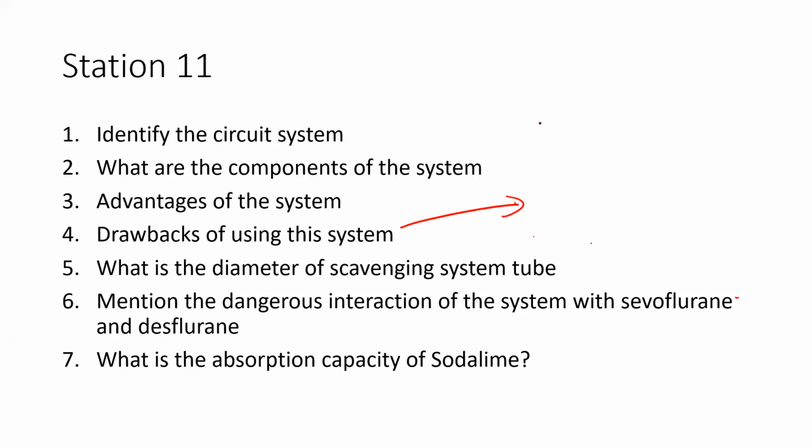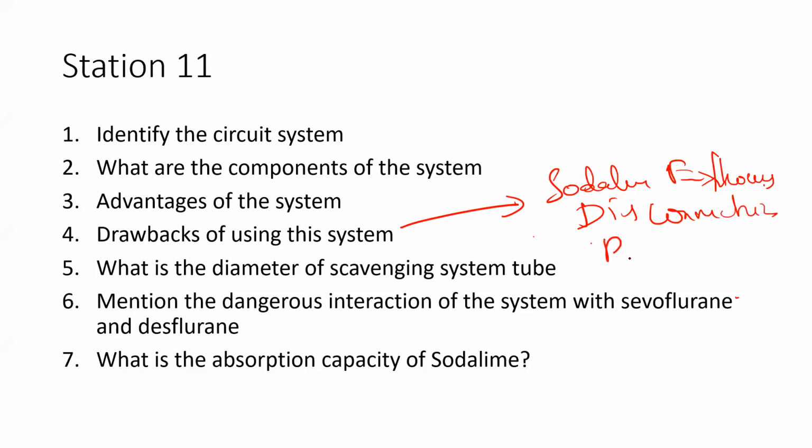Disadvantages are that it may cause exhaustion of soda lime, which may cause an increase in EtCO2. Okay, soda lime can get exhausted. Multiple connections, so chances of disconnection in the circuits. Fine. Heavy weight, bulky circuit, yes. Very important. It is bulky, it is not portable, so you can't utilize it except in the operation theaters. Then hypoxic gas mixture delivery in case of low flow. Many people are telling this.